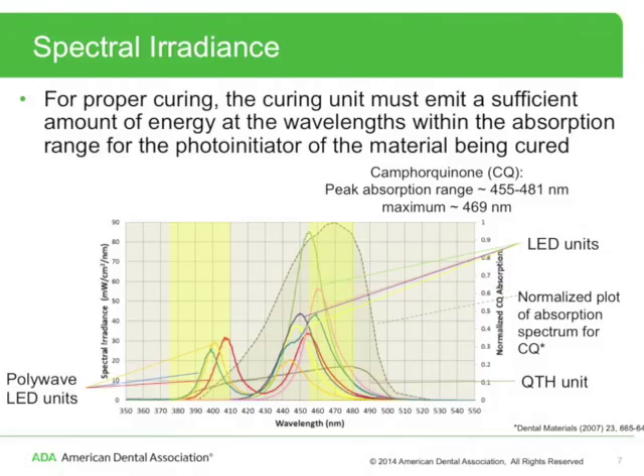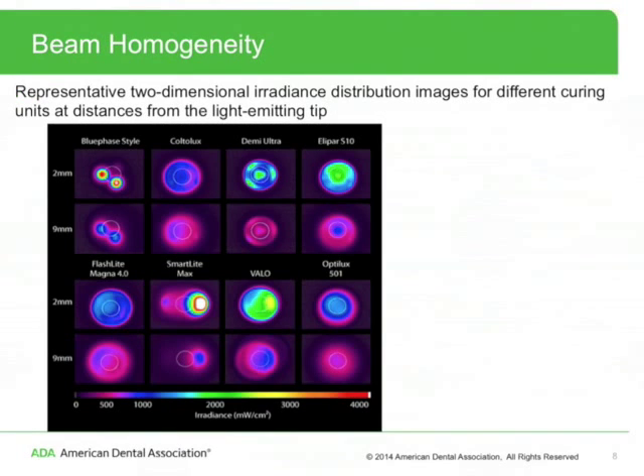In the figure, the poly-wave LED units have a peak centered at around 398 to 408 nanometers. These curing units are designed to work with photo initiators other than camphorquinone. There is a yellow shaded region from about 375 to 410 nanometers that approximately represents the absorption range for the photo initiator Lucirin TPO.